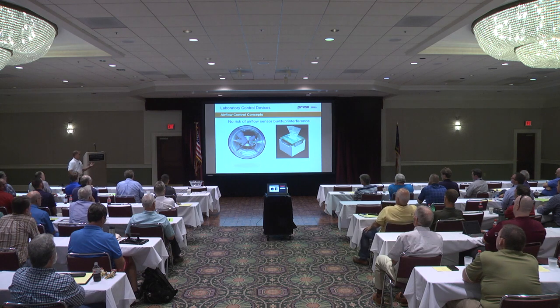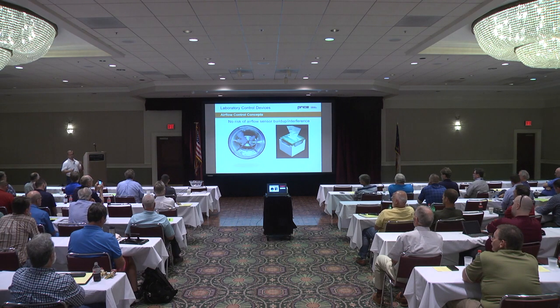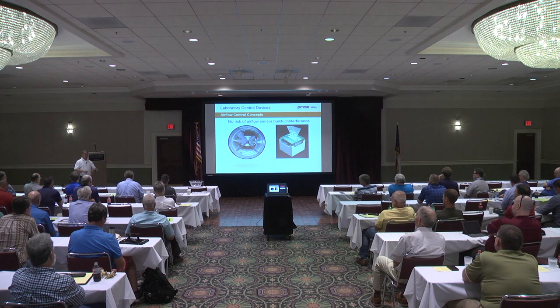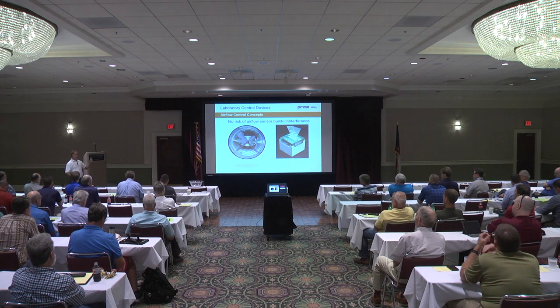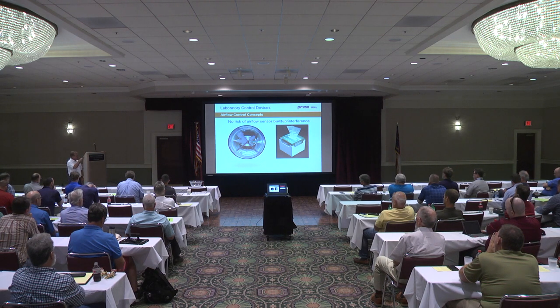You have your hospital rooms, your bedding every day. They're changing the bedding, or twice a day, or who knows, whatever the frequency is. But anyway, they're bringing bedding in. Bedding is letting off lint. As soon as they make that bed up or throw the old sheets off, put the new sheets on, lint is continuously cycling through that room. Well, it's going up into the duct, and it's going to cake at some point in time, continually adding to that flow ring or that flow sensor device.